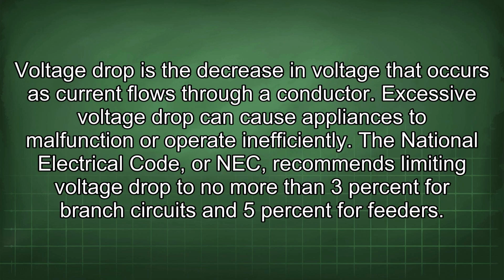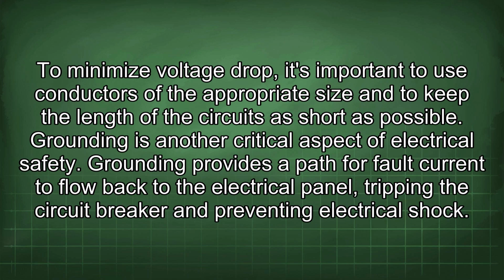Voltage drop is the decrease in voltage that occurs as current flows through a conductor. Excessive voltage drop can cause appliances to malfunction or operate inefficiently. The National Electrical Code, or NEC, recommends limiting voltage drop to no more than 3% for branch circuits and 5% for feeders. To minimize voltage drop, it's important to use conductors of the appropriate size and to keep the length of the circuits as short as possible.